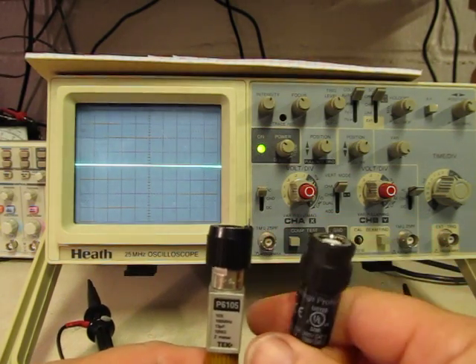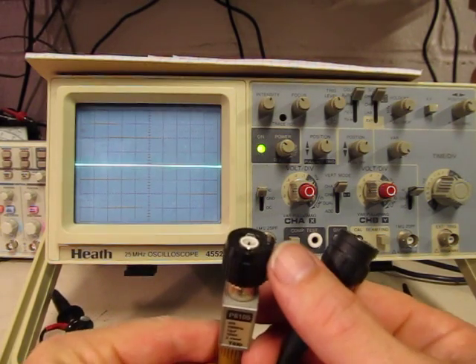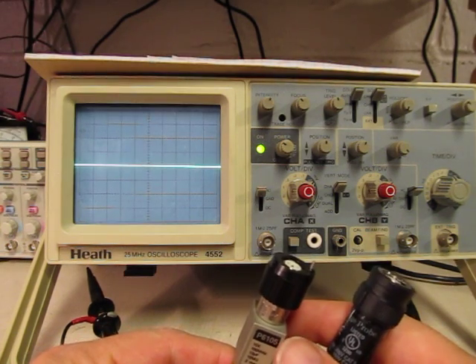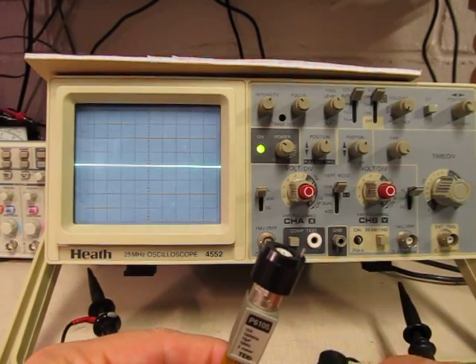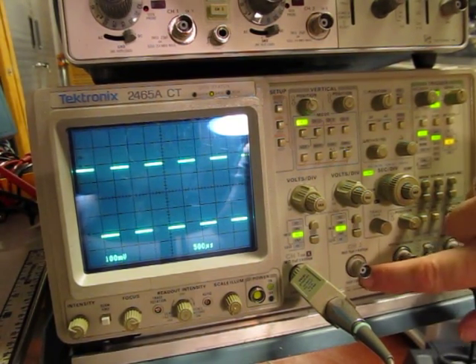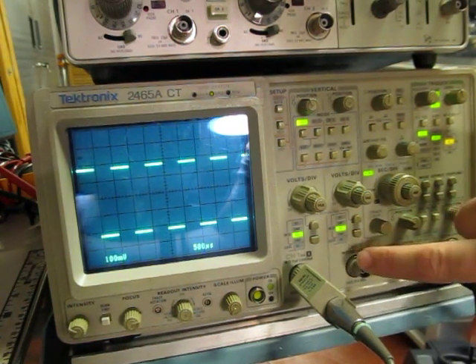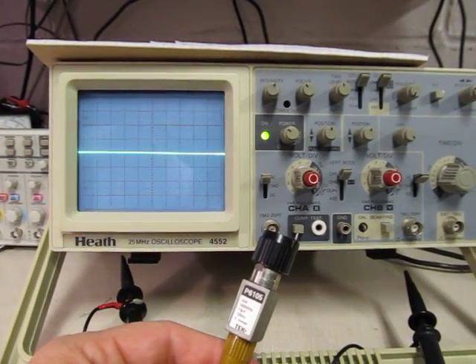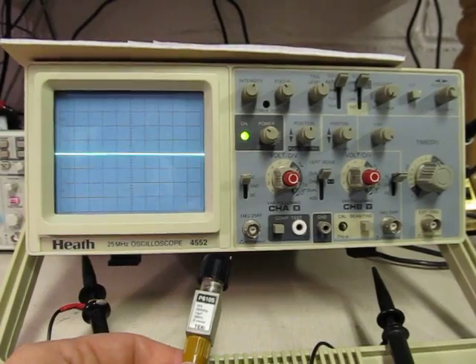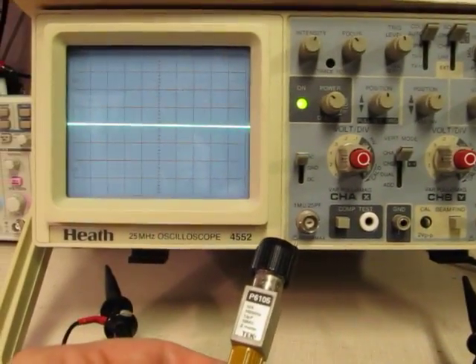But one thing I wanted to point out that's different between these two. If you look carefully at the end of these, there's a little metal pin sticking out of this one. There's a little metal pin sticking out of the end of the connector here. And what that is, it's something that Tektronix called the TekProbe interface. And for scopes that were so equipped, when you connected this probe up to the scope, the scope had a little sensing ring. In fact, we can look at that over on this scope over here. There's a little sensing ring right around the BNC connector here. And that BNC connector, when that little pin connects to that, that would tell the scope that this is a 10X probe that's being attached. And it'll adjust the scale appropriately. Most scopes, especially non-Tektronix scopes, don't have that little sensing ring around the BNC connectors where you connect the scope up.